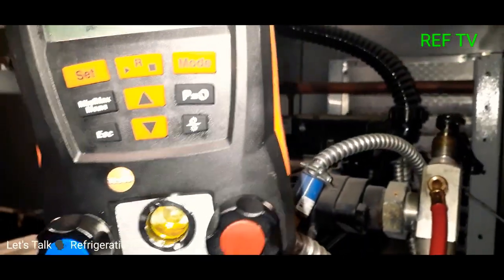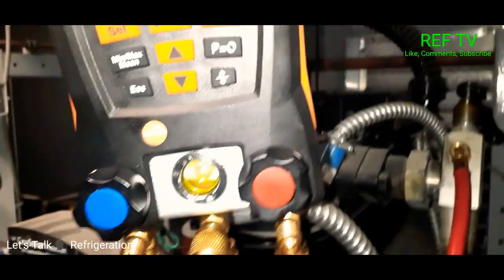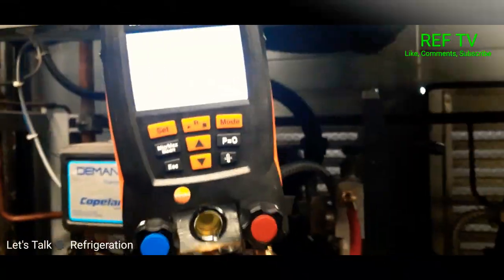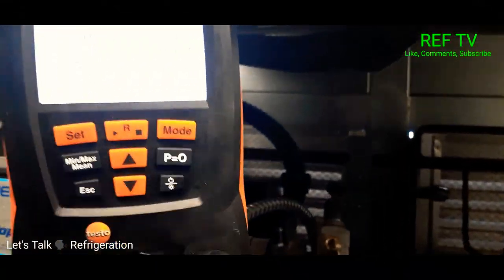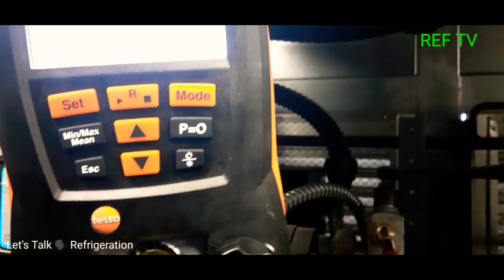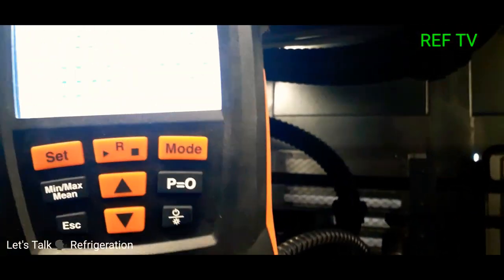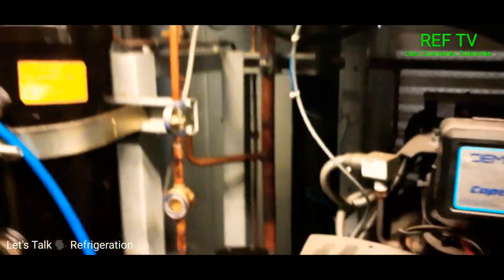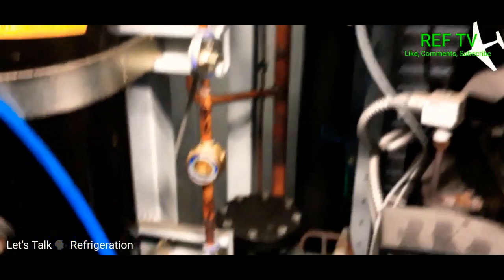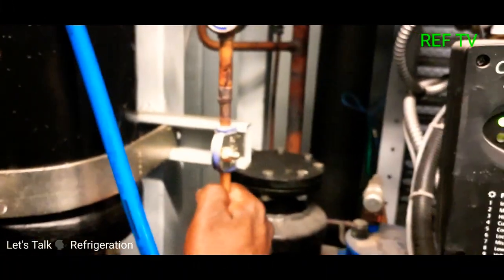Like I say, we might not even have to go as high as 250 head pressure. So we're at 262. You see our head pressure went up tremendously. We're almost up 100 PSI. And like I told you, this line here is hot now. So I believe that's good enough. Let's just go ahead and back this up.